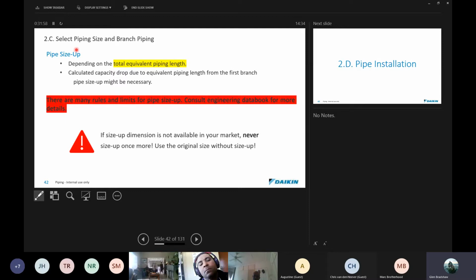All right, so what happens in the instant where we have to do a pipe size up? Well, this will depend on the total equivalent piping length. And the calculated capacity drop due to equivalent piping length from the first branch pipe size up might be necessary. There are many rules, okay, and limits for pipe size up. Consult the engineering data book for more details, or else chat to one of your sales engineers or one of the service engineers as well, and ask them as soon as you consider that you might be in a dangerous area. If the size up dimension is not available in your market, never size up once more. Use the original size without sizing up.